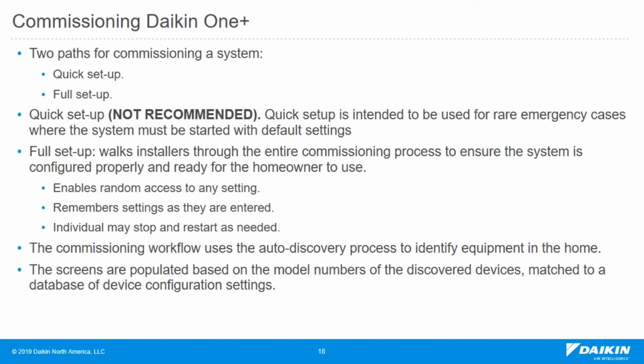The commissioning workflow uses the auto discovery process to identify equipment in the home. So when you do put it on, it may take up to 20 minutes to discover all the equipment. It will communicate. It will keep reaching out and looking over the network for any other equipment. It also checks an internal database. So when you go to install the system, if there's a mismatch, it tells you we have a system mismatch and this will not operate.